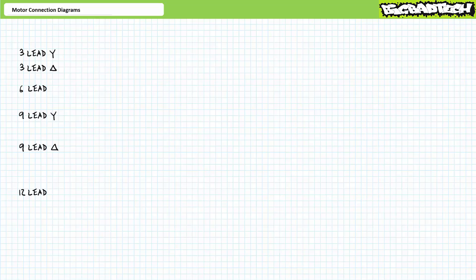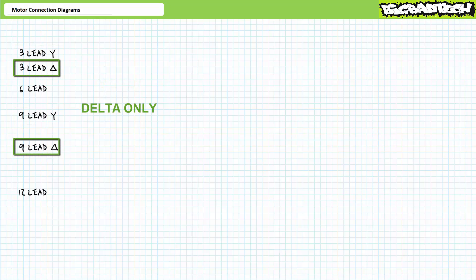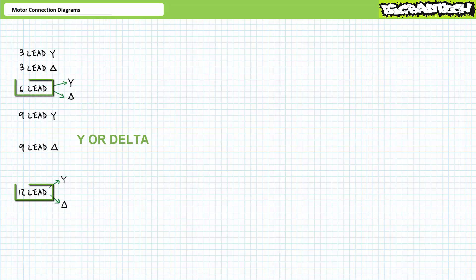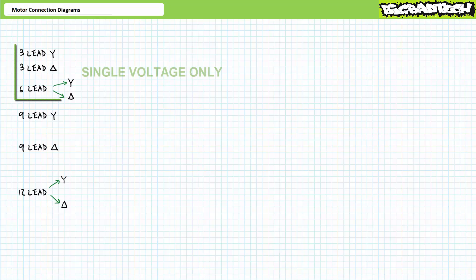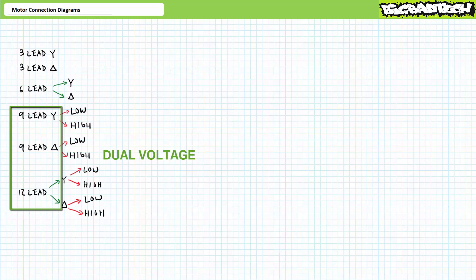We'll examine each option in detail, but let's divide these into general classes regarding their electrical configuration and whether they are intended for single or dual voltage systems. Three-lead Y and nine-lead Y motors are permanently pre-configured as Ys. Three-lead delta and nine-lead delta motors are permanently pre-configured as deltas. Six and twelve-lead motors can be hooked up in either Y or delta fashion. All three-lead and all six-lead motors are intended for single voltage operation, whereas nine and twelve-lead motors are intended for dual voltage operation.